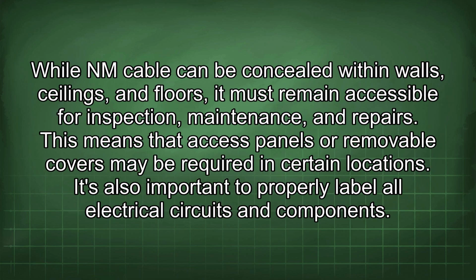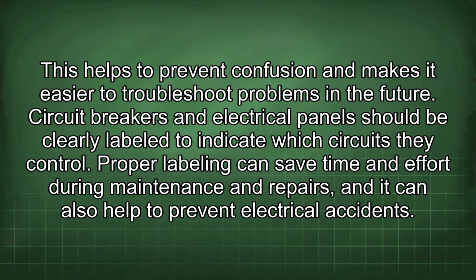While NM cable can be concealed within walls, ceilings, and floors, it must remain accessible for inspection, maintenance, and repairs. This means that access panels or removable covers may be required in certain locations. It's also important to properly label all electrical circuits and components. This helps to prevent confusion and makes it easier to troubleshoot problems in the future. Circuit breakers and electrical panels should be clearly labeled to indicate which circuits they control. Proper labeling can save time and effort during maintenance and repairs, and it can also help to prevent electrical accidents.